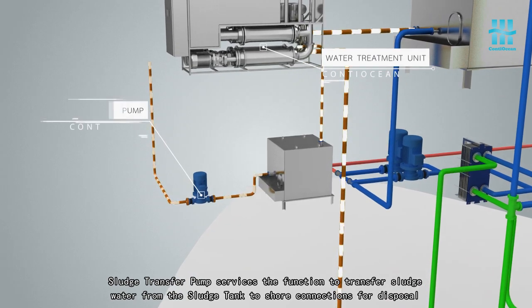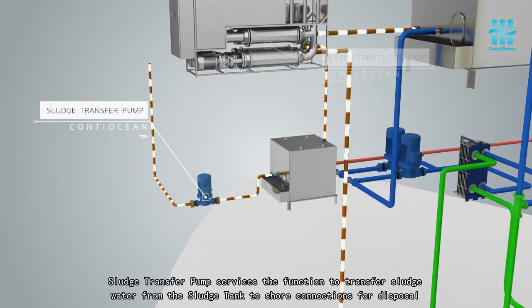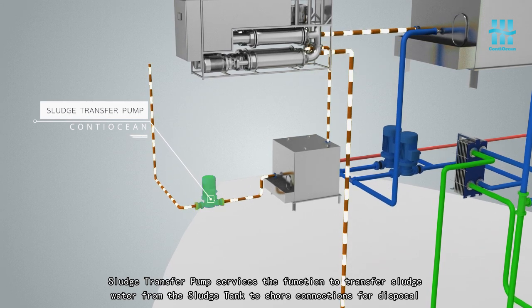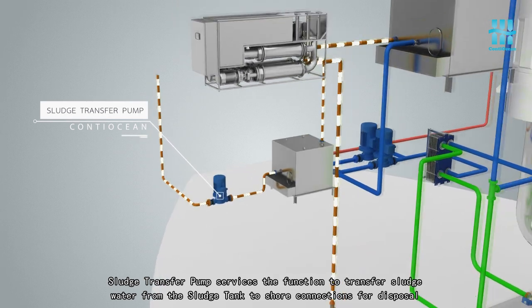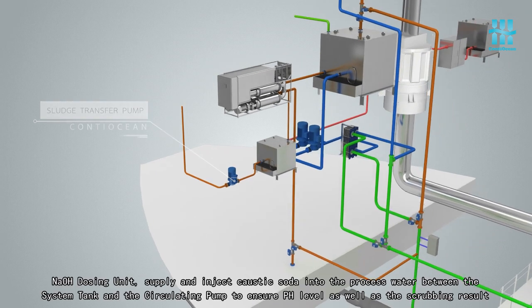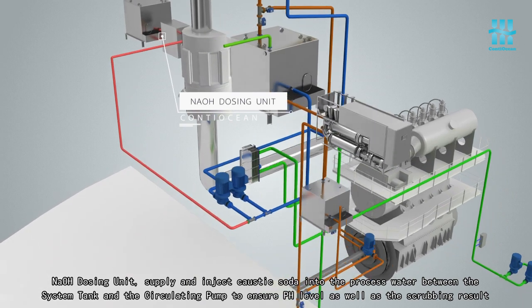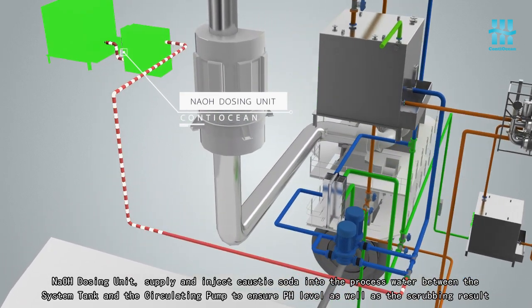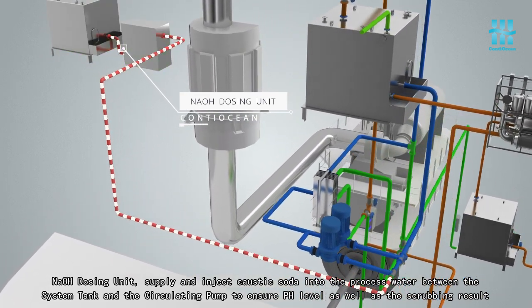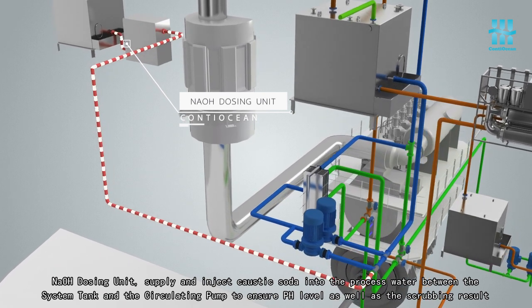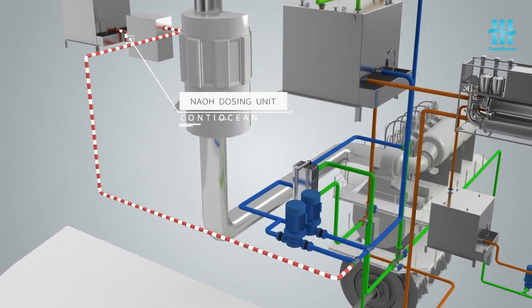Sludge transfer pump services the function to transfer sludge water from the sludge tank to shore connections for disposal. NaOH dosing unit supply and injects caustic soda into the processed water between the system tank and the circulating pump to ensure pH level as well as the scrubbing result.